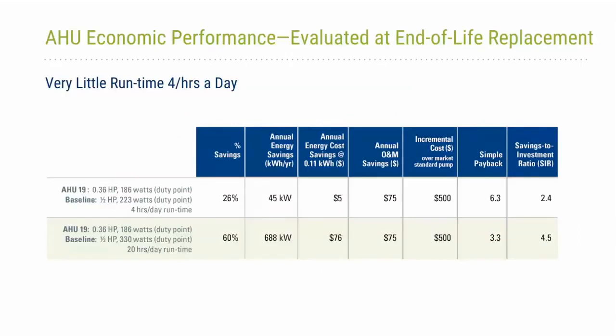So on the economics of this one, the first line just walks through what the annual cost savings were. Again, they're extremely low on the energy cost savings because the pump really doesn't run much. But assuming the O&M savings for this, we still have a good simple payback. The incremental cost is also lower because for domestic hot water recirculation pump applications, you have to have a stainless steel pump. And for heating hot water, you can use a cast iron pump, so it's a cheaper pump.